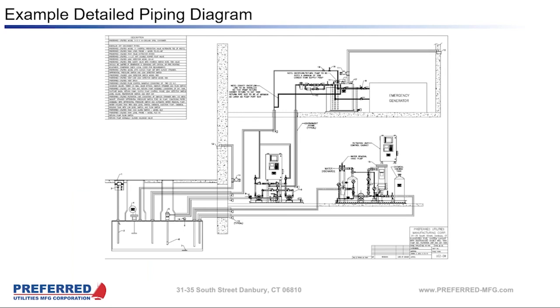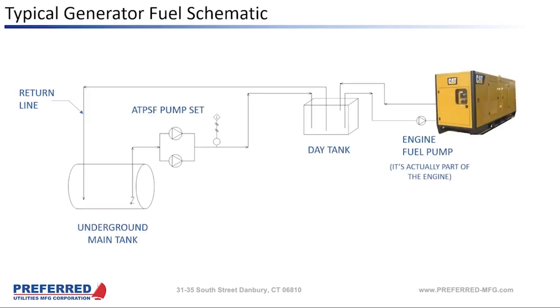So this is just a typical piping diagram. It's a little hard to read, but we've got a pump set in the center pulling out of an underground storage tank, and then pushing fuel up to an emergency generator inside of a building. And that whole assembly on the right is a big fuel polisher that removes the water, and this one adds a chemical agent to the fuel too. This diagram is a schematic that shows how we typically will pipe a fuel system for an emergency genset. And I wanted to show this slide and the next one so that you're familiar with how we typically pipe these systems, and then some of our cold weather strategies will make more sense.